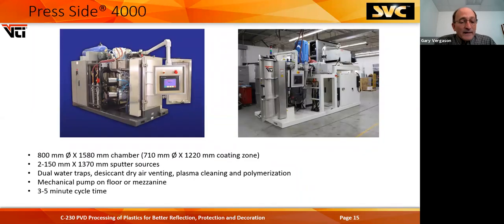Machines keep getting bigger. Parts got bigger. They got more complex. They're wrapped. Some of these parts are 20-some inches long, and they're a foot deep. So the chamber had to increase in size. We added water traps to help pump water vapor out of the system. This blue tank is a clean tank that stores desiccant dried air that we power vent the system back with. So the system comes back from vacuum to atmosphere in about 9 seconds.